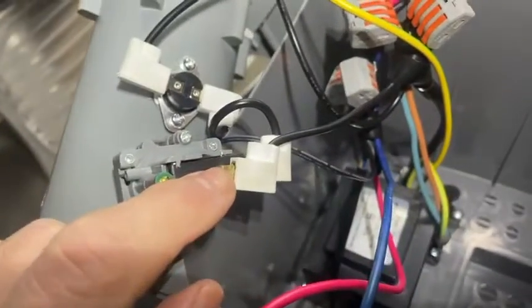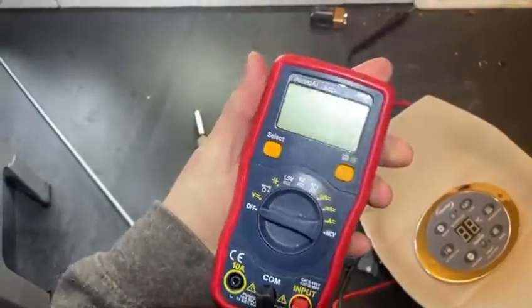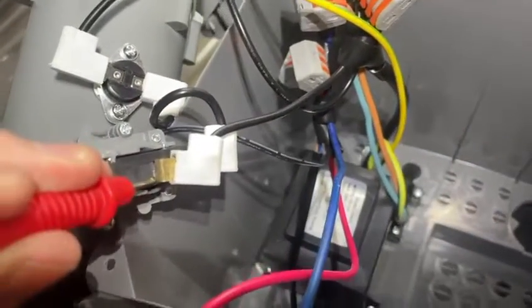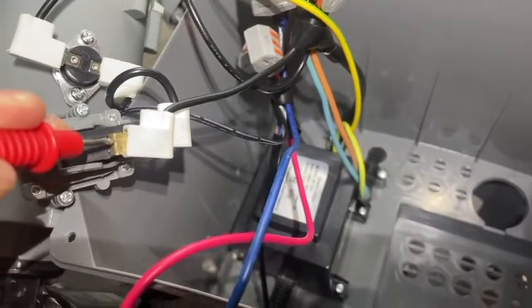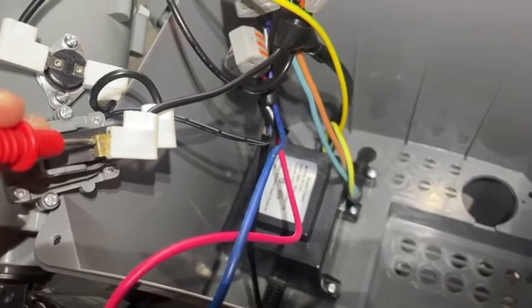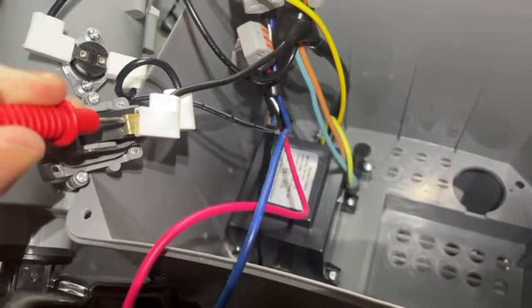So what you can do to test that - this should be an open circuit at the moment because there's no water in the reservoir. So get yourself a multimeter if you've got one, set it to continuity test, and then test these two terminals. Make sure if it's not beeping, you know that's an open circuit.